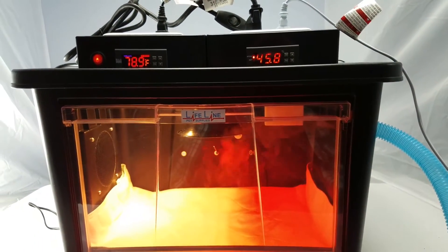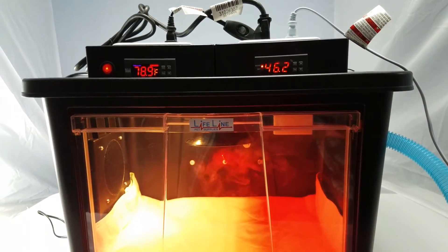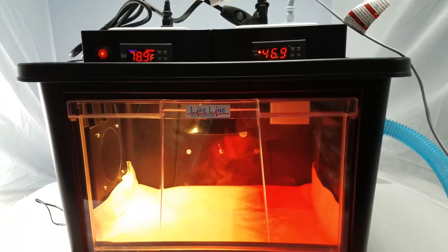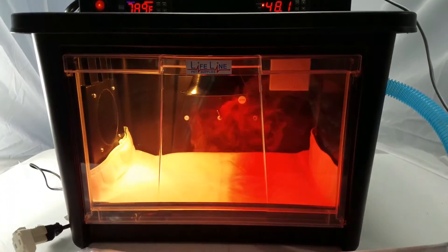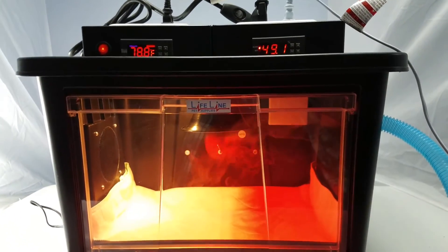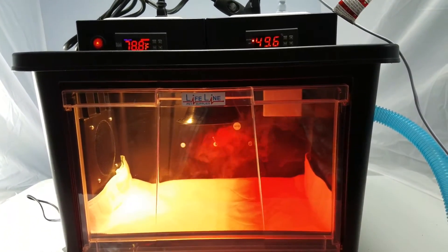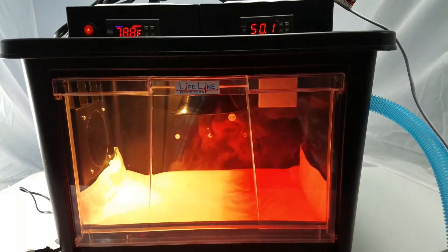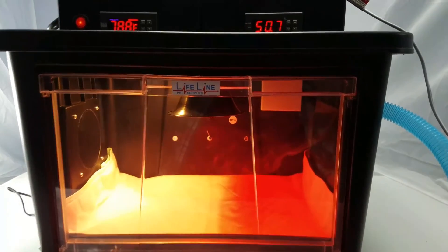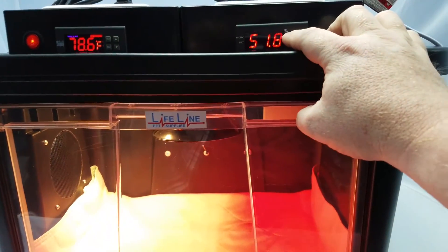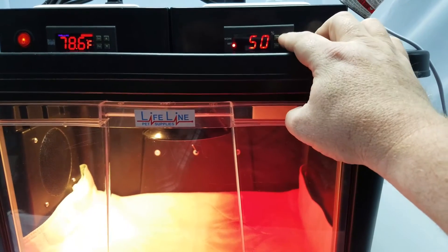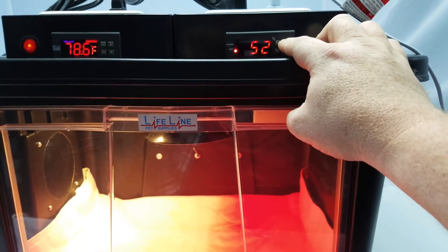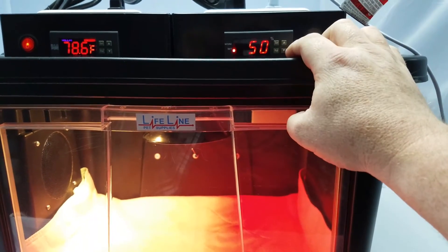That's going to keep that humidity regulated inside the unit. You want it between about 40 and 60 percent, so we set the target for 50. And to change that setting on your controller, just hit the set button one time, use your up or down arrows for where you want to put your humidity percentage at, and then hit set again.